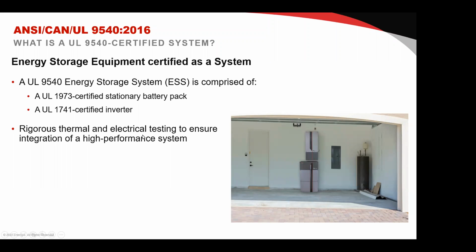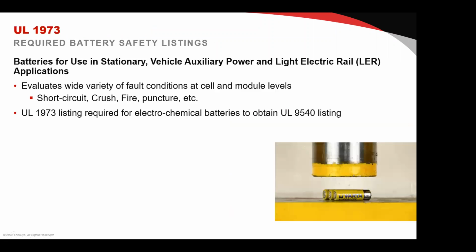Okay, so there's a lot of testing it does: thermal testing, electrical testing, crush proof testing, and we'll just jump to this next slide here. The UL 1973 requires battery safety listings where a lot of testing is done, including this crush test you can see in this little graphic here on the bottom right. And it's looking for short circuit, crush, fire, puncture, outgassing, flammable gases, that sort of thing. So it is required to obtain a UL 9540 listing.